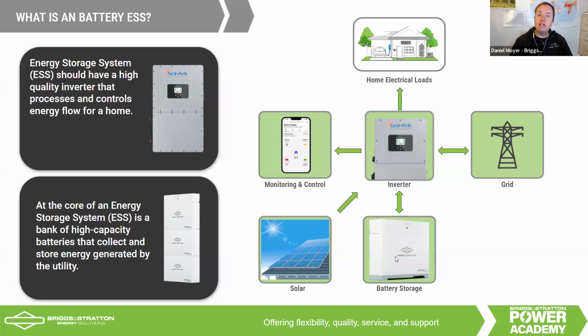Then when you need to use it, you take that DC, turn it into AC, and power the home loads. With our charge controllers and DC coupling, we're able to take the solar DC and feed it directly into the battery as DC, avoiding inverter losses. We're also able to avoid some inverter clipping. So it's more efficient to do it this way.